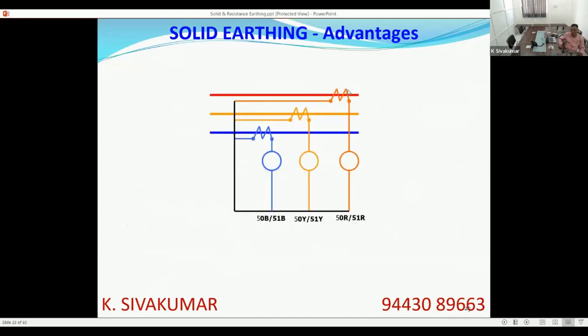Even in the system, if that happens to be an earth fault, you don't need an earth fault relay even, because the current involved is in kiloampere. The fault feeding phase will also sense the kiloampere current, and any relay or fuse you provide in the phase itself will open the breaker or the fuse will blow out, thus isolating the faulty zone. Very quick time it will do.